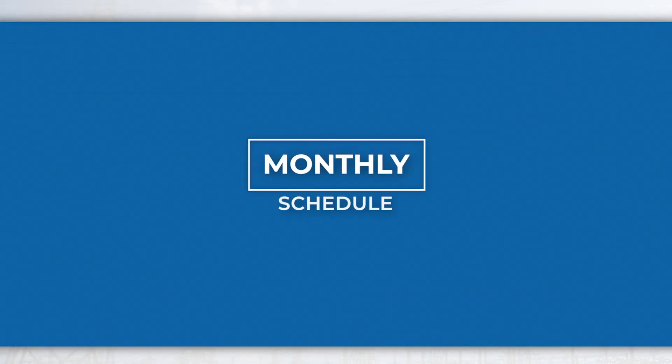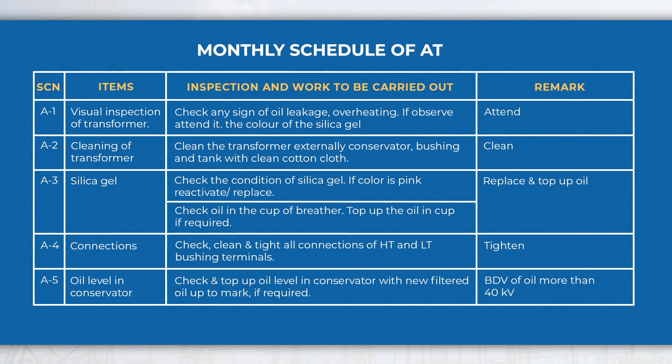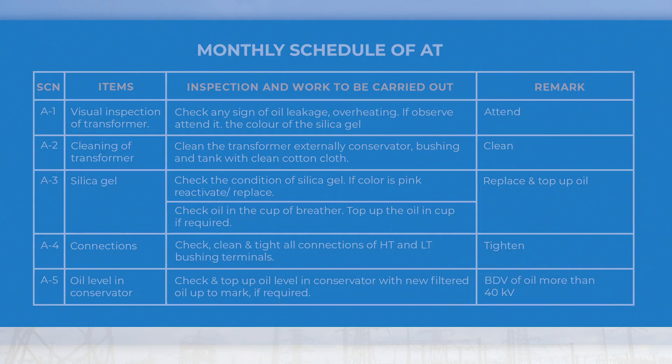In the monthly schedule, perform activities like checking the oil level in the conservator, condition of silica gel, fuse and HT/LT bushing terminal connections, etc.